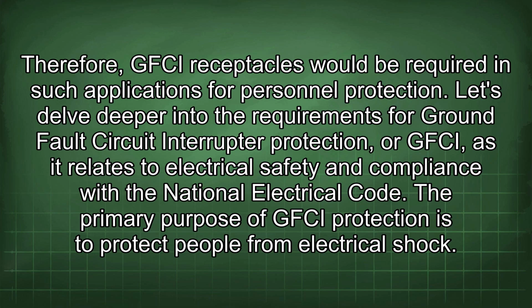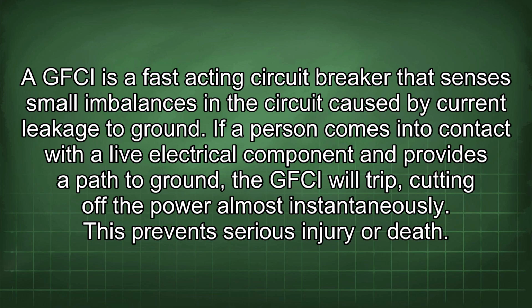Let's delve deeper into the requirements for ground fault circuit interrupter protection, or GFCI, as it relates to electrical safety and compliance with the National Electrical Code. The primary purpose of GFCI protection is to protect people from electrical shock. A GFCI is a fast-acting circuit breaker that senses small imbalances in the circuit caused by current leakage to ground. If a person comes into contact with a live electrical component and provides a path to ground, the GFCI will trip, cutting off the power almost instantaneously. This prevents serious injury or death.